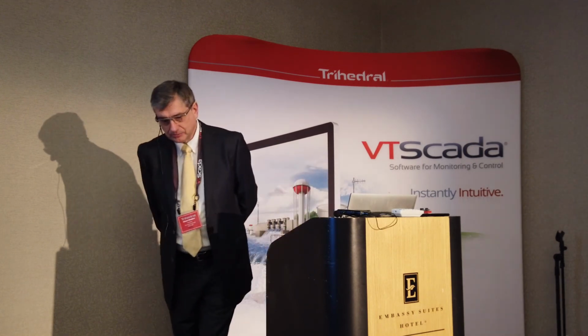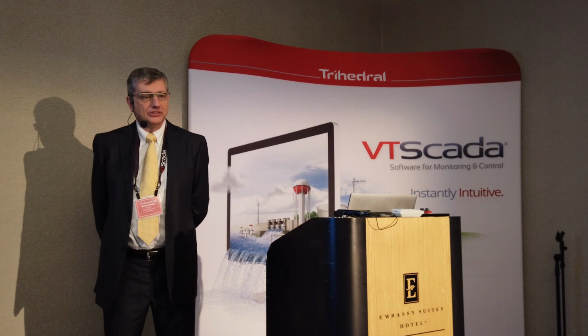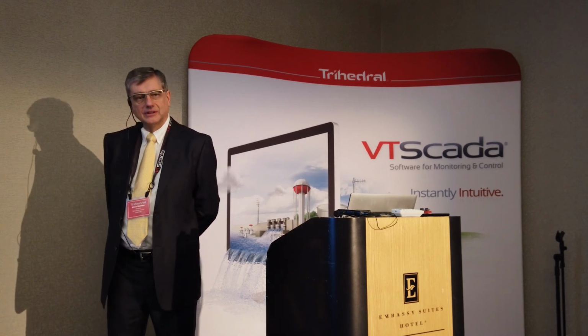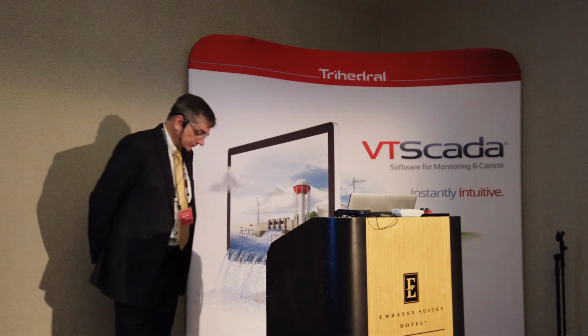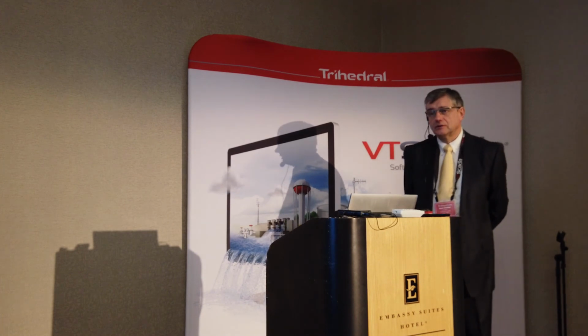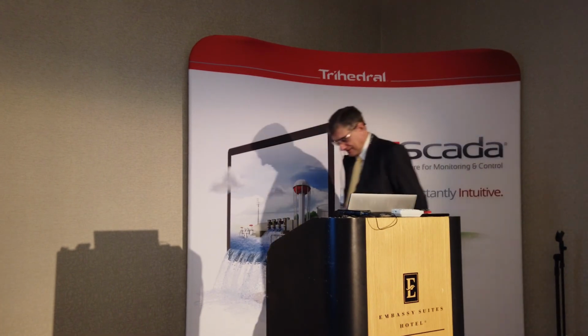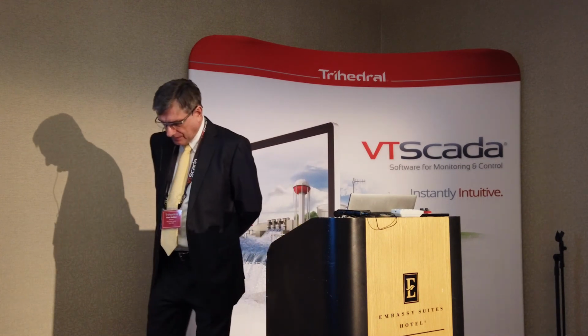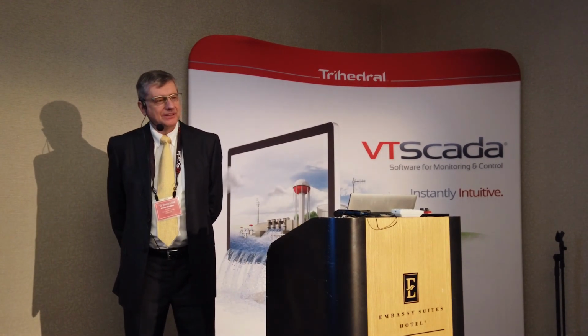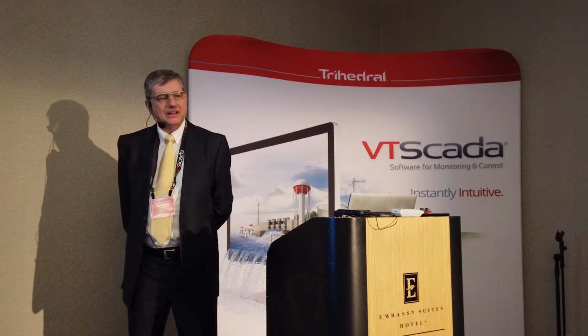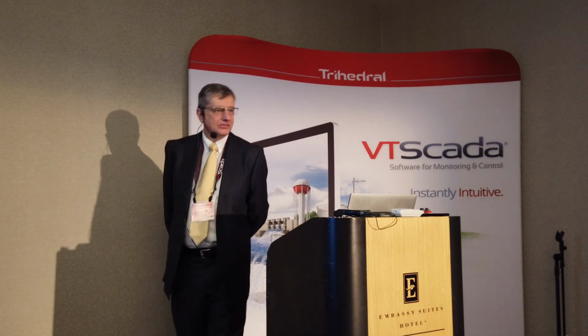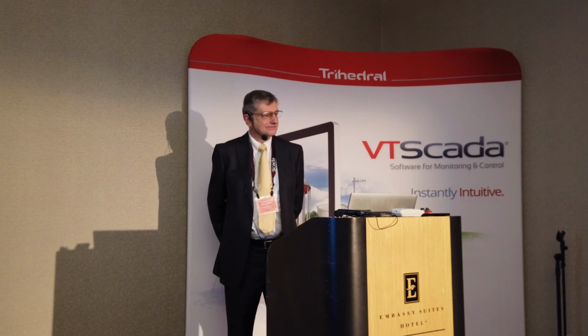Other things you probably do want to see, because there's some high-speed machinery where having high resolution history on it is valuable. I've had one of our customers out of California that runs monitoring on GE gas turbines. They are high-speed rotating machinery, highly dynamic. They're basically jet engines running generators, and they record their data every 1/10 of a second, because when things go wrong, they go wrong fast, and they want to see how things go off.